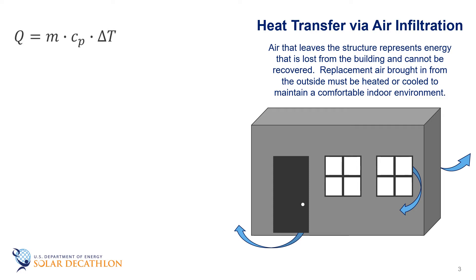The amount of energy required to heat this air is governed by its mass times its specific heat times the change in temperature. If we look at this as a rate of heat transfer into the infiltration air, we can take the derivative of both sides of the equation, and assuming that the change in temperature is constant and the specific heat is constant, we see that Q̇ equals ṁ Cp ΔT. This is called a mass flow rate since we're looking at the rate at which the mass of air is entering the building.